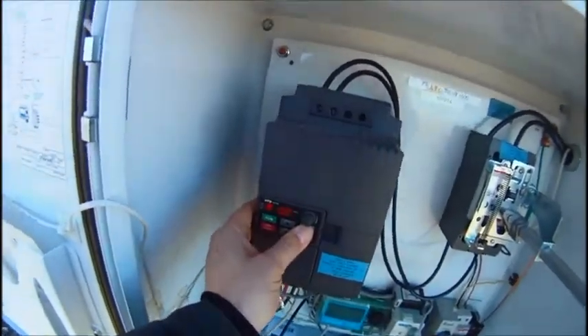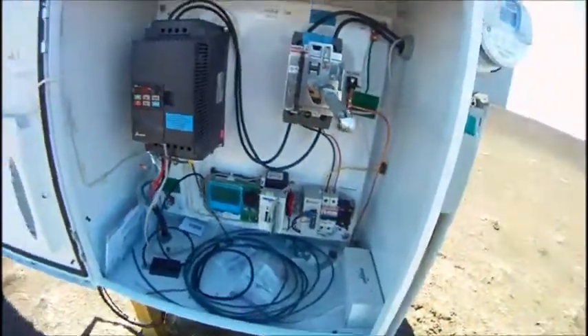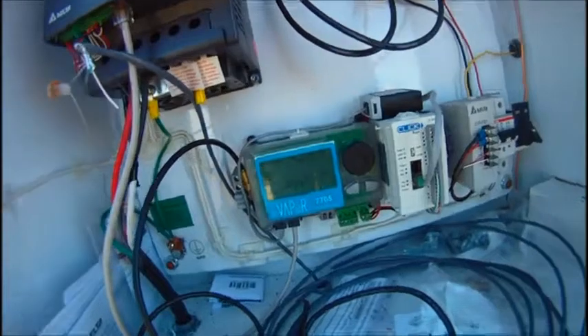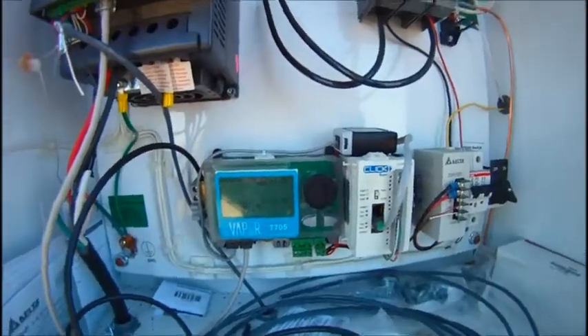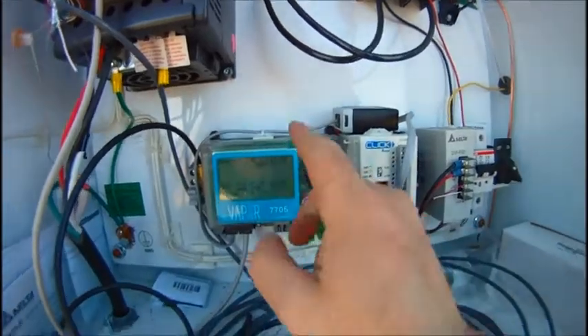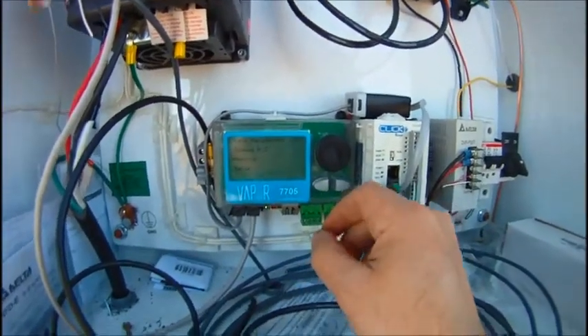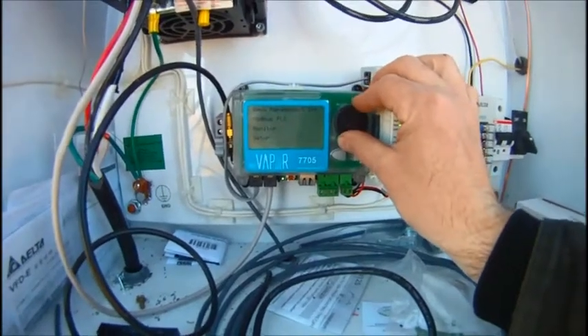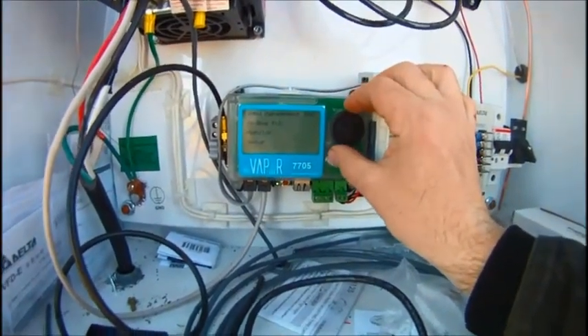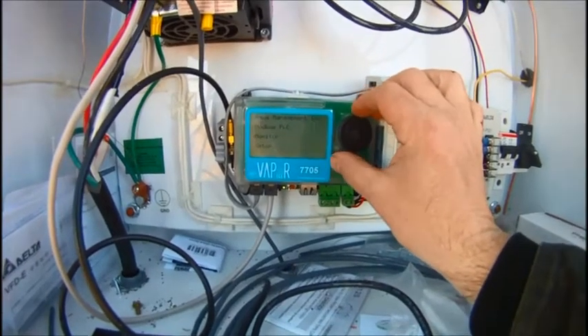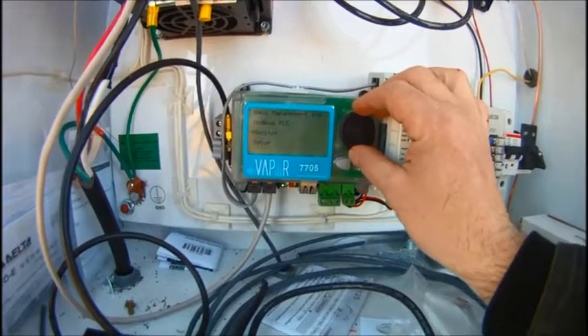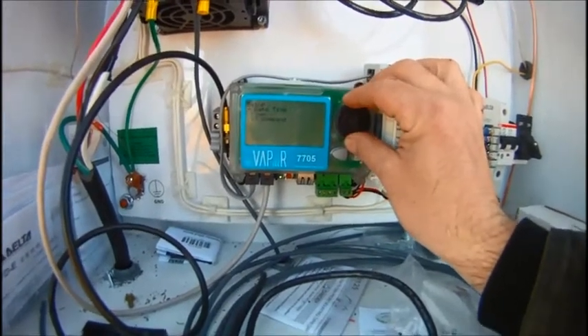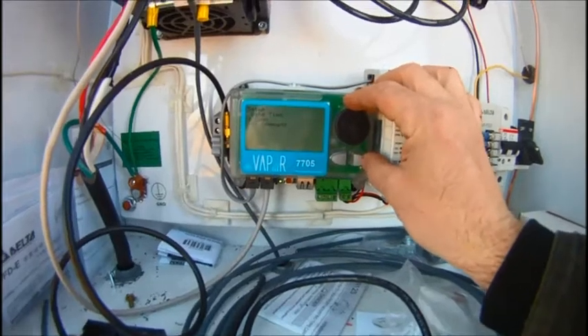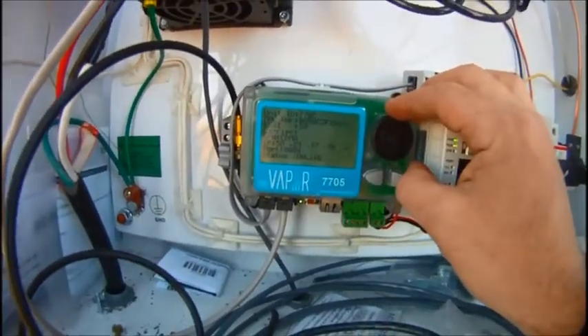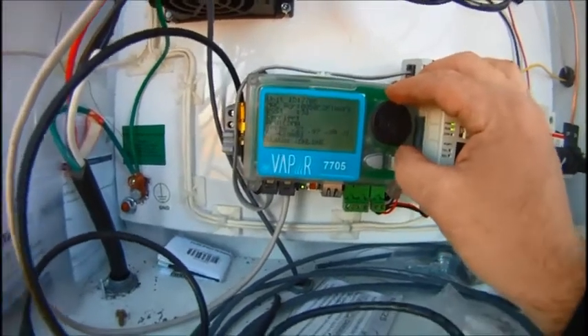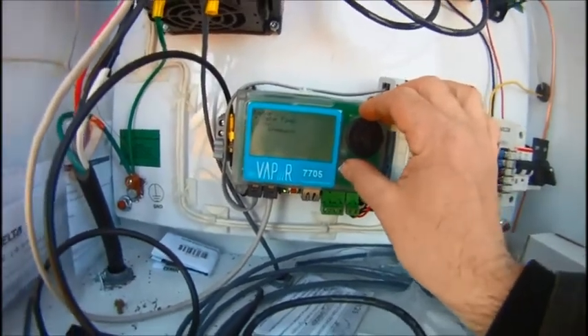So we'll double check what our transducer is reading. It should be 0.0, which it is. One other thing we'll double check is our receiver strength of our AMI remote monitoring unit here. And we'll hit this button and we'll go to setup. Hit your right button when you're on setup. You go to COM, hit your right button. Your receiver strength is at 30, which is pretty good. So we'll hit left to get out of there.